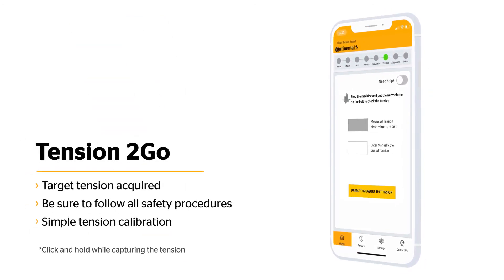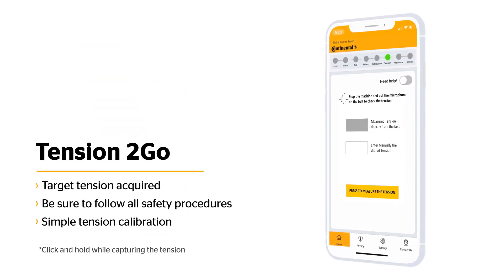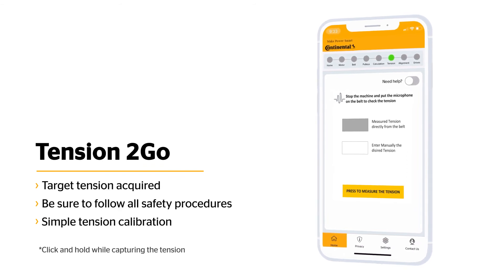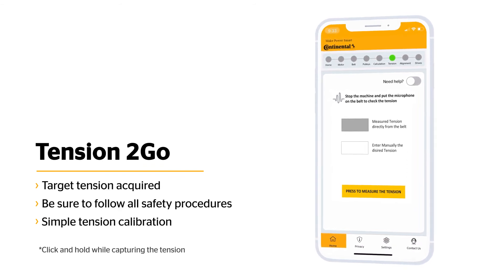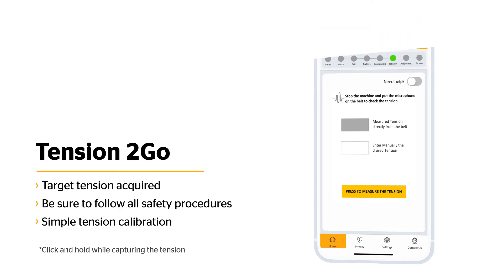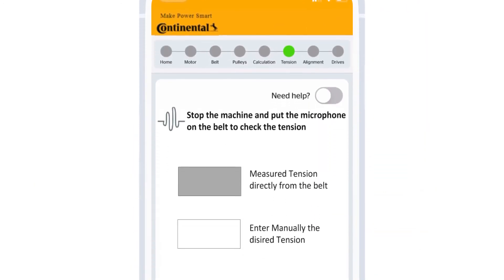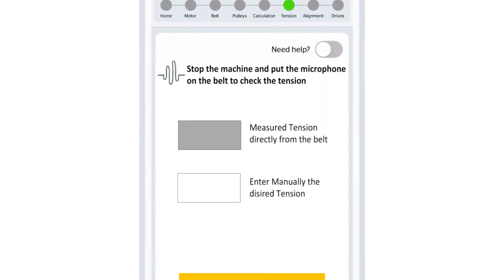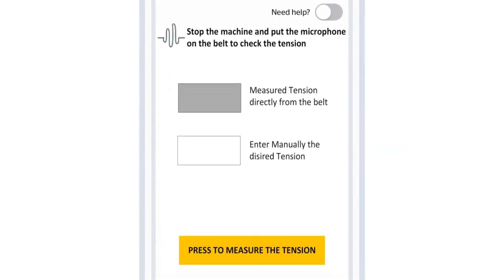Based on the details collected so far, we now have our target tension for a new belt installation. Before removing a belt guard, be sure to follow all lockout and tagout safety procedures. Then click Measure Tension.